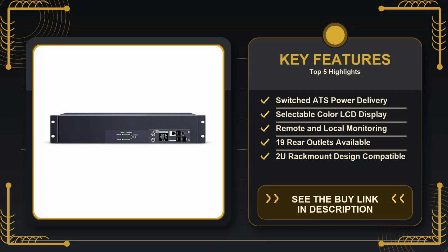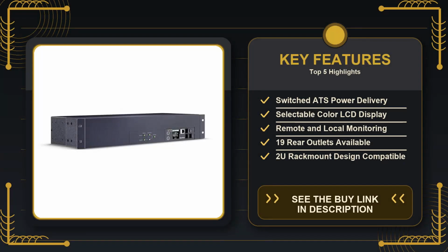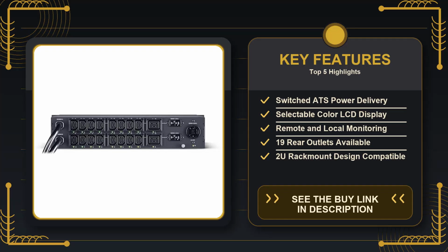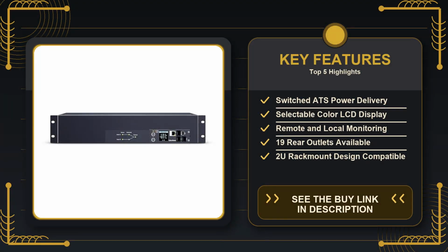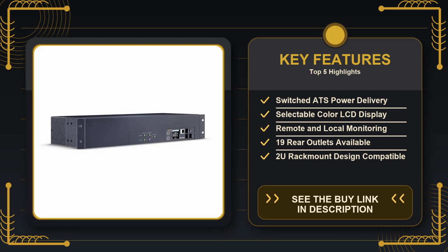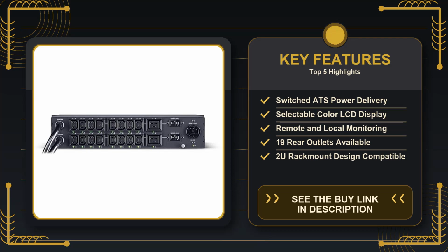On the flip side, there are a couple of practical trade-offs that you need to keep in mind. The unit is rated for 30A but is derated to 24A. That's a nuance you'll see in the spec sheet, but it matters when you're planning the total load on the rack. If you're feeding a collection of devices that together can pull close to 30A under peak conditions, you'll need to either limit the number of devices or ensure the upstream circuit can safely handle the continuous 24A draw.